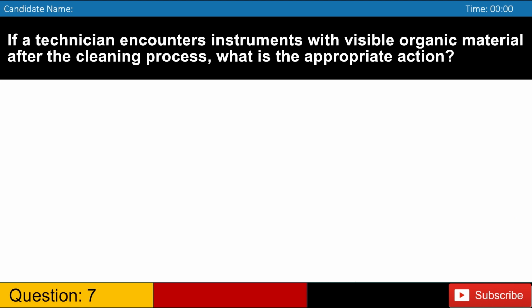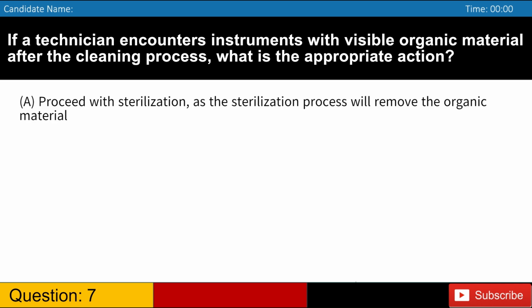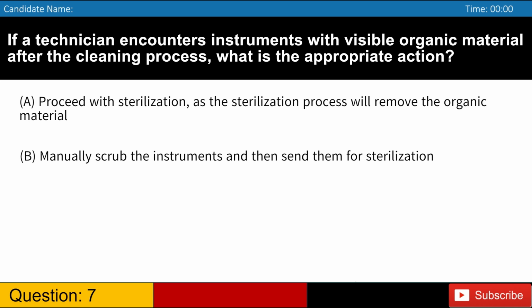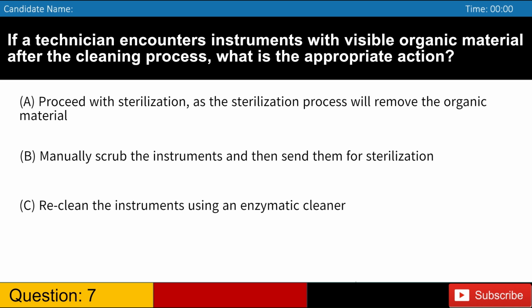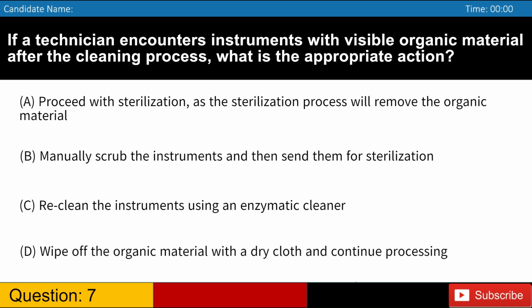If a technician encounters instruments with visible organic material after the cleaning process, what is the appropriate action? A. Proceed with sterilization, as the sterilization process will remove the organic material. B. Manually scrub the instruments and then send them for sterilization. C. Reclean the instruments using an enzymatic cleaner. D. Wipe off the organic material with a dry cloth and continue processing.